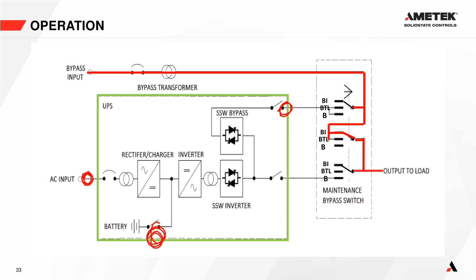Or if we really needed to, if this UPS was obsolete and needed to be replaced, we could disconnect all the cables here, the battery cables, these cables, and these cables. We could remove this UPS, install a new one, connect all the cables back up, test it, make sure everything's good, and then following the procedure, put the bypass switch back into the normal position.